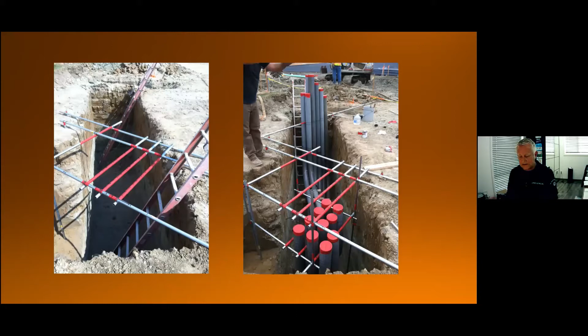We tie them down heavily because when conduits are grouped up in this manner, they require slurry encasement, a concrete sand slurry. It can be chipped away, but it dries hard, close to concrete. There's so much air in the conduit that it will float as you're pouring the sand slurry, so it's important that we tie them down tightly. Otherwise, if they float, you've lost the job, and have to remove the slurry, dig back down, put the conduit back in, and re-slurry. That's an important task for the sand slurry.